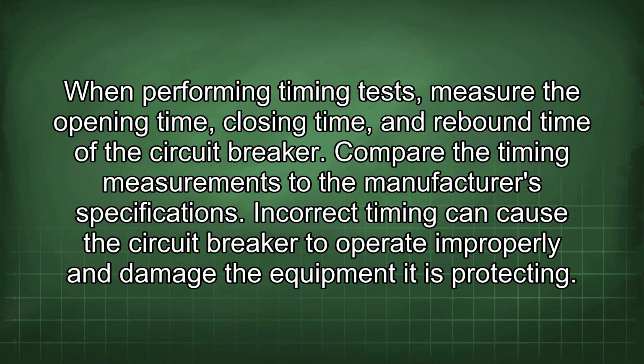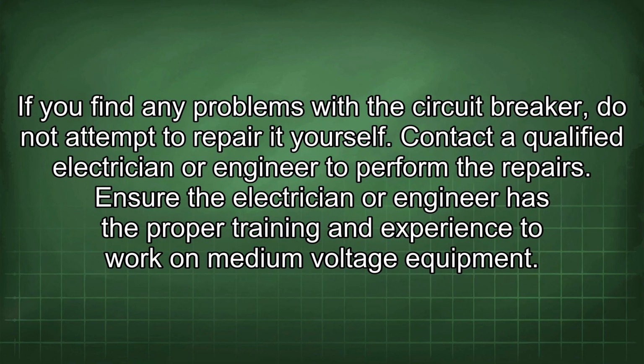When performing timing tests, measure the opening time, closing time, and rebound time of the circuit breaker. Compare the timing measurements to the manufacturer's specifications. Incorrect timing can cause the circuit breaker to operate improperly and damage the equipment it is protecting. If you find any problems with the circuit breaker, do not attempt to repair it yourself. Contact a qualified electrician or engineer to perform the repairs. Ensure the electrician or engineer has the proper training and experience to work on medium voltage equipment.